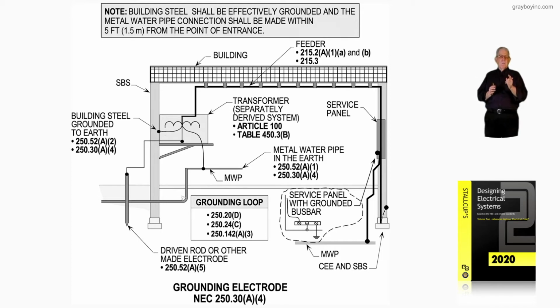250.30(A)(4) deals with the separately derived system, but notice in 250.50, 250.52, and 250.53, you're dealing with the service equipment to the right. And notice we are connecting into an electrode system there. It could be a concrete encased electrode, it could be the structure building steel, it could be a water pipe, any of those that are listed in 250.52(A)(1) through (A)(7). But now notice we have a feeder going over to that transformer primary.